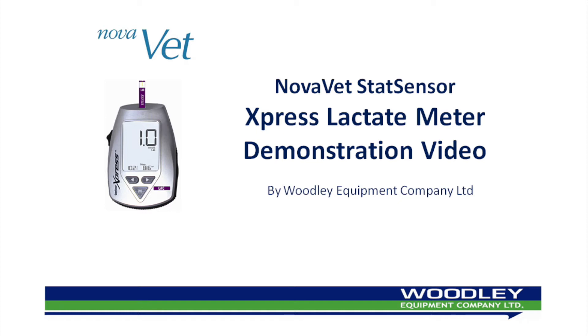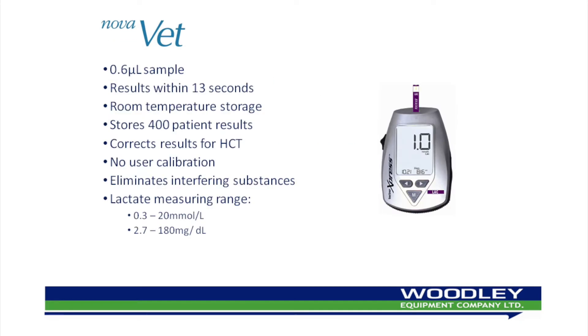Welcome to the NovaVet StatSensor Xpress Lactate Meter instructional video, brought to you by Woodley Equipment Company Limited. The NovaVet StatSensor Xpress Lactate Meter is an easy-to-use, portable, battery-powered meter that works in conjunction with the NovaVet Lactate Test Strips to measure blood lactate. The NovaVet Lactate Meter uses only 0.6 µL of sample to achieve a result in 13 seconds.